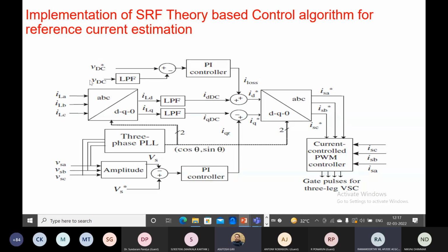So the DC link reference and actual values are compared, the error is processed through the PI controller, and the PI controller generates an active current component equal to the loss component in the inverter. This represents how we generate the active component demand for the generator, since the generator also supplies real power for the inverter component.